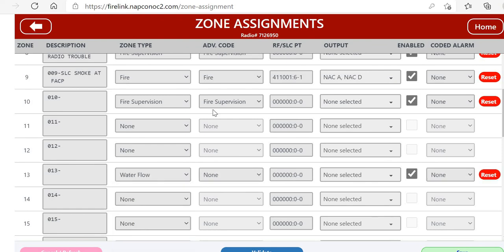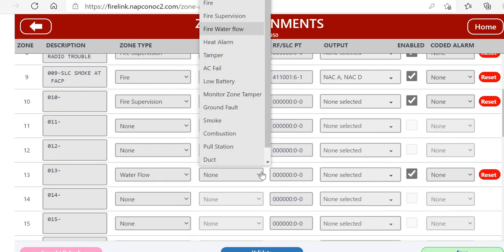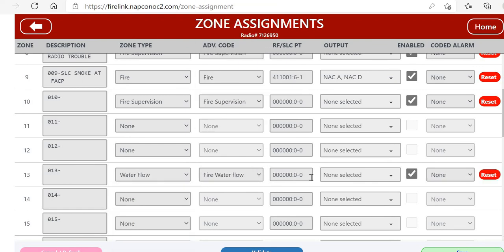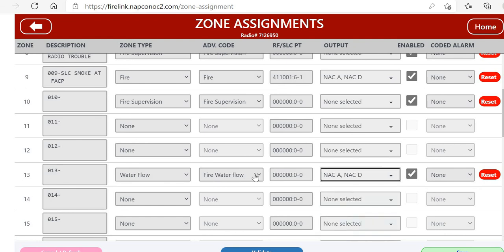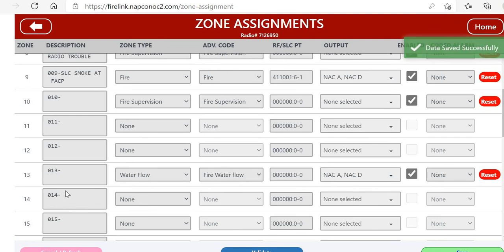Then we would go back to our Zone Assignment section and we would start now on zone 13 because that's our first EZM zone. Same thing, you could make it a water flow. It's an EZM, so it's not going to have an RFSLC point. You would just pick the NACs that you want it to sound off and then click Save. Same thing, own description.